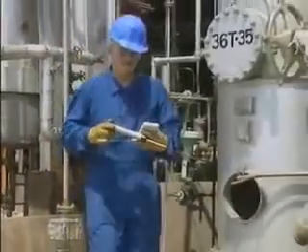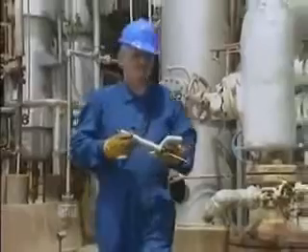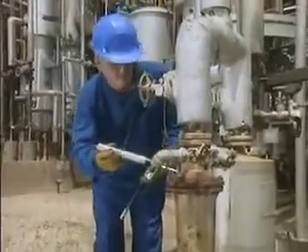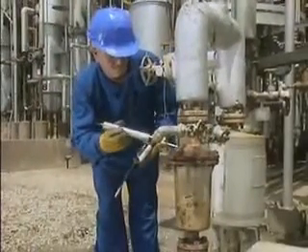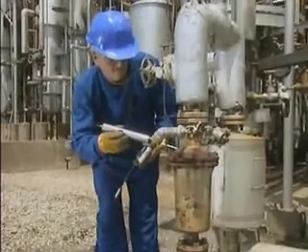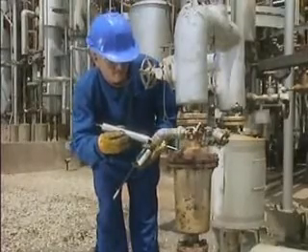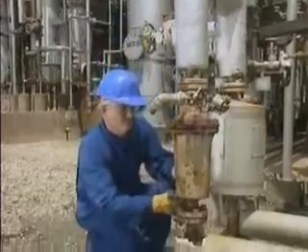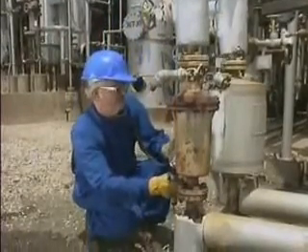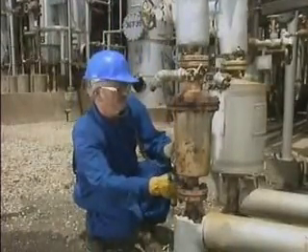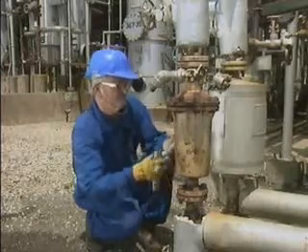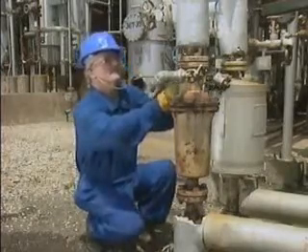By combining the information you get from performing temperature, sound, and visual inspections that you make during a trap survey, you can get a good idea of how well a specific trap is working. Trap surveys should be performed on a regular basis. A trap's size, pressure, and workload will determine exactly how often a survey should be conducted.